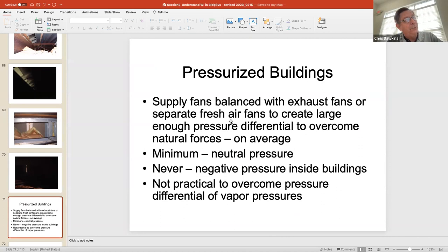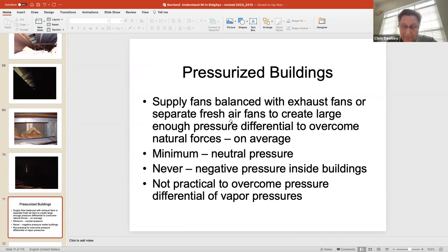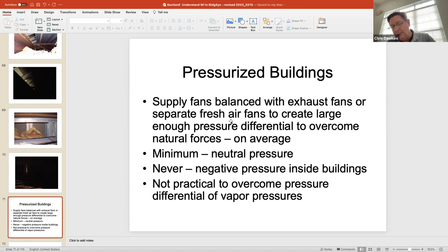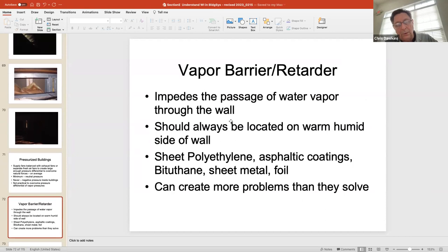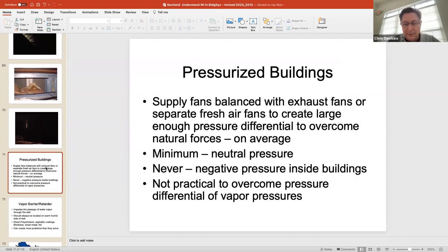Pressurized buildings: if the supply and return systems of the HVAC are not in balance — say the supply provides 80 CFM but the returns pull 100 CFM — that 20 CFM difference is going to be pulled in from wherever the leaks are. This is a big issue with commercial buildings and some residences. Essentially, if you've got negative air pressure and air leaks, you're pulling unconditioned air into the building — and it's kind of game over.